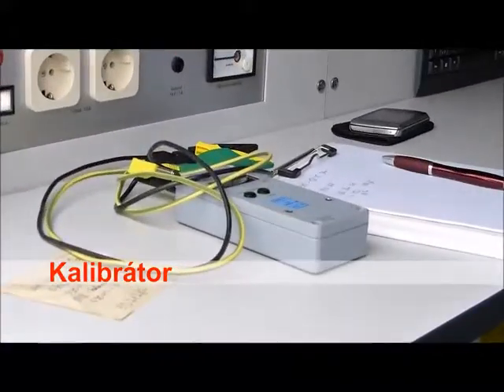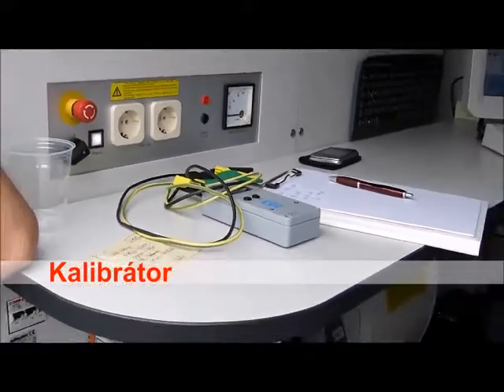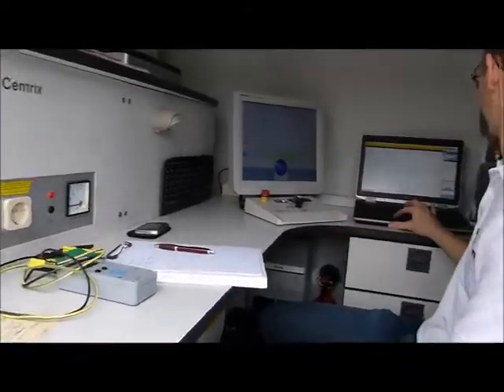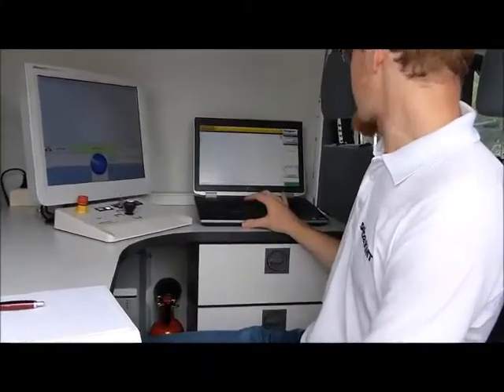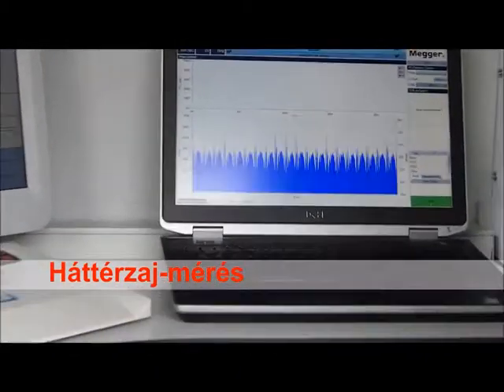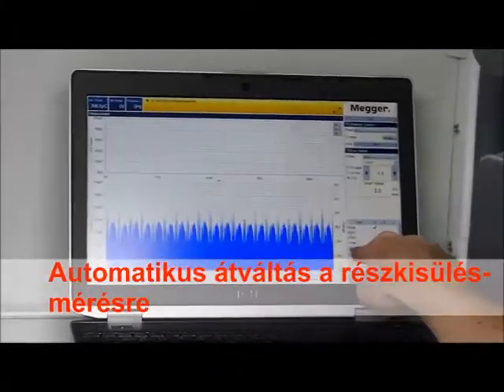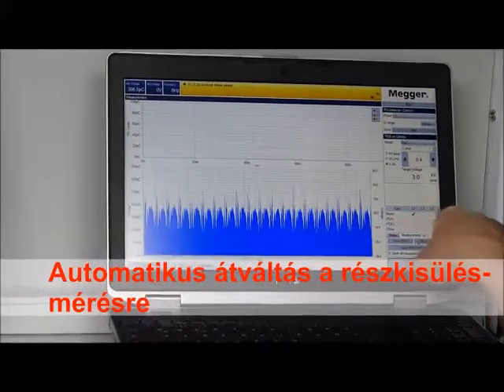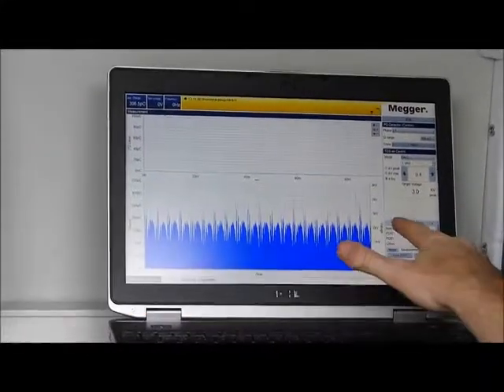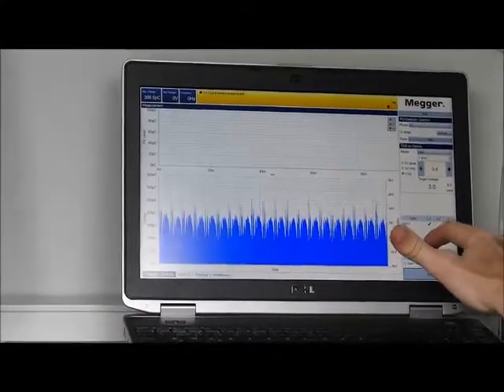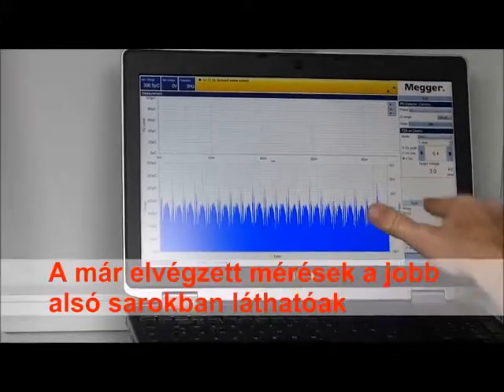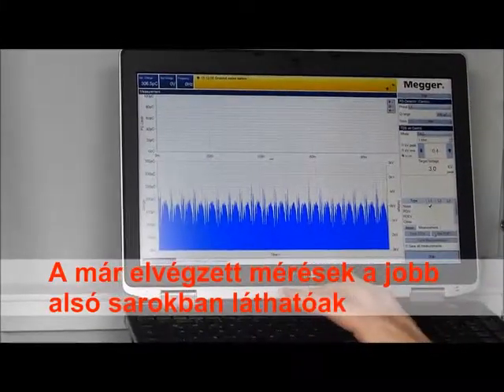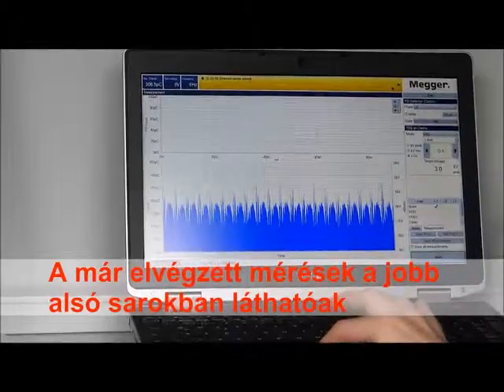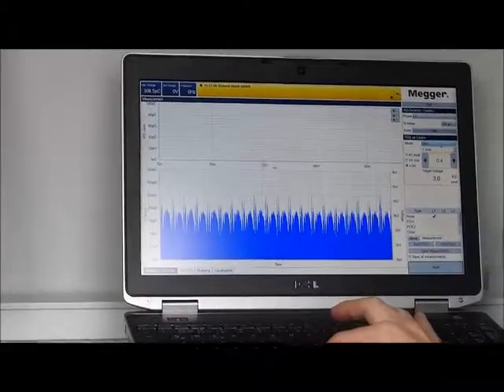And always, when we make a measurement, like also with the OWTS, we start with the 0 kV. So we make a background noise measurement. So we save it, and automatically it switches from noise measurement to a real partial discharge measurement. And you see also for you as information we have done, okay, noise measurement check mark for phase 1. So you have a list, okay, what I have to do already.